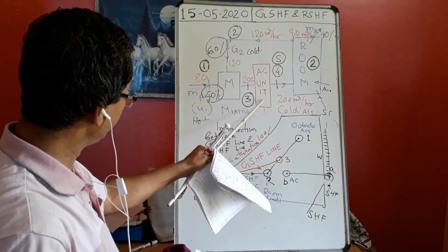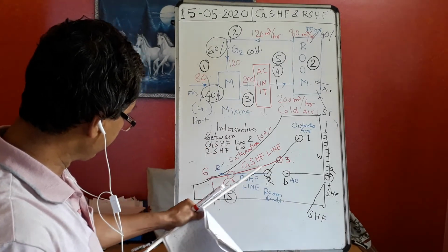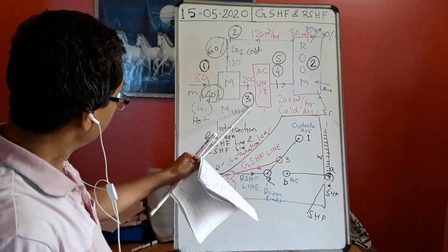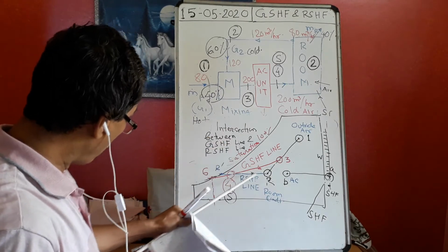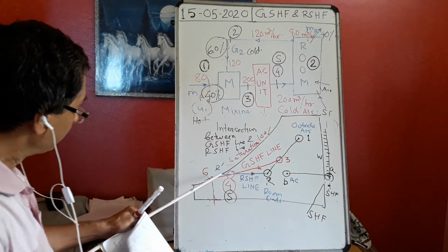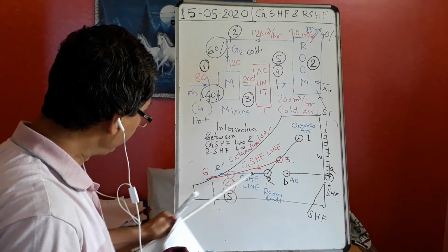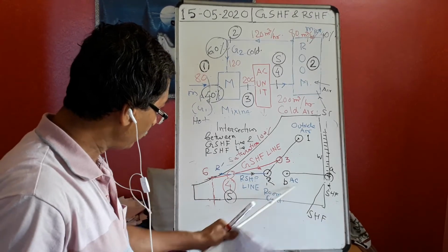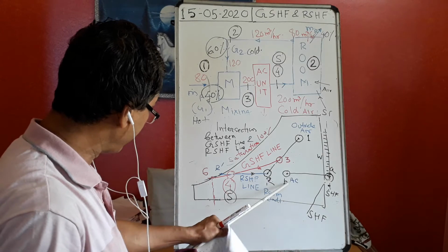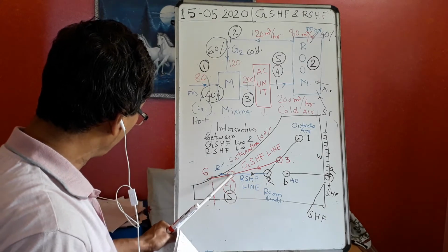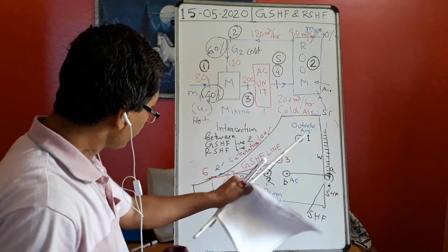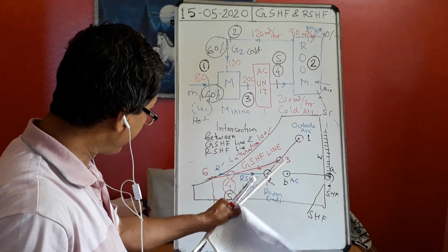They go to the AC unit for cooling. So cooling is taking place along this line. But how far it will go, I do not know. How do I find the supply point? I find the supply point after knowing the GSHF line and the RSHF line, and where they cut, I get the 4. So that means the fresh air is coming here.